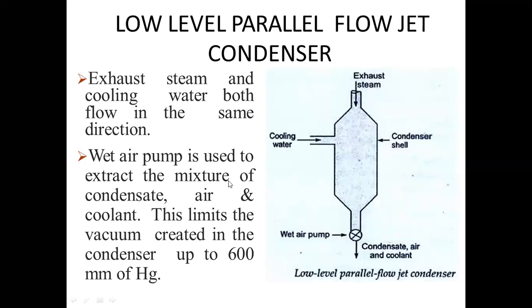A wet air pump is used to extract the mixture of condensate, air and coolant. This limits the vacuum created in the condenser up to 600 mm of Hg. This is parallel flow. It can also be counterflow. In case of counterflow, cooling water enters from the top side wall and hot exhaust steam enters from the bottom side wall. So in this case also they come in direct contact.